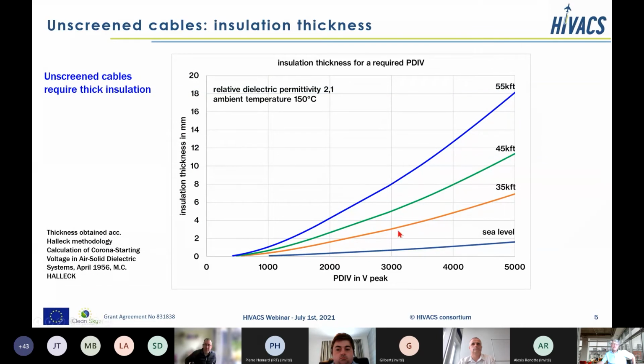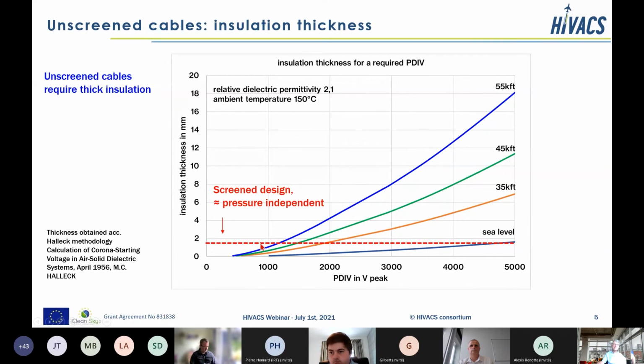So here we see estimated insulation thicknesses in millimeters for a required partial discharge inception voltage. So we see that the higher the voltage, the thicker the insulation has to be. And of course, the higher the altitude or the lower the ambient pressure, the thicker the insulation needs to be. So if we focus here on, for example, the 2 kilovolt PDIV, then we would need an insulation thickness of roughly 4 millimeters.